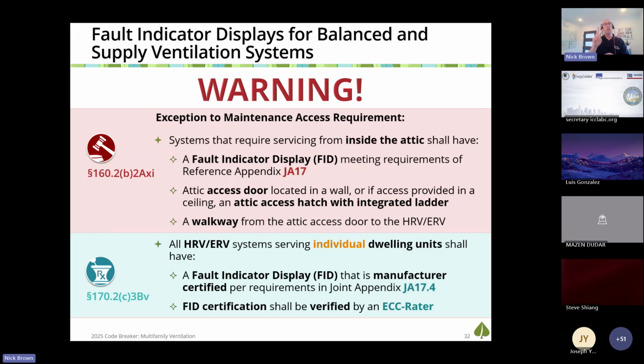So there's two scenarios where FID may be required. One, if you've got a system in an attic, that FID needs to provide a signal to the occupants that something's wrong with the system. There needs to be an attic hatch with integrated ladder and a walkway from the access to the unit. So that's a mandatory requirement if you have your ventilation system located in an attic.